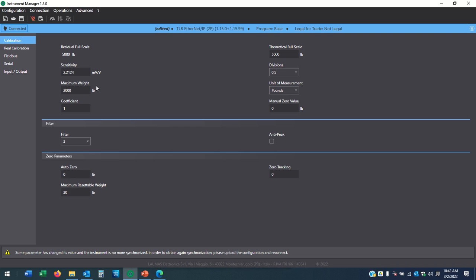So I can actually reduce the range, which is not only going to help its overrange capability, but it gives me the ability to have one load cell act and operate like a wide range of load cells. Again, I told you that you can choose your type of output in pounds, newtons, kilograms, grams, whatever you want. So we're going to do pounds, which is good. And I've got filtering here. So filtering at 0 means I'm going to get roughly 500 hertz. If I put some filtering on, it's going to be a much more stable signal, but it might not update quite as fast. And then I've got an auto zero here that says, when I auto zero it, it had better be within, say, 5 pounds. If it's greater than 5 pounds, don't allow it to zero. So that's how you would calibrate this thing manually.